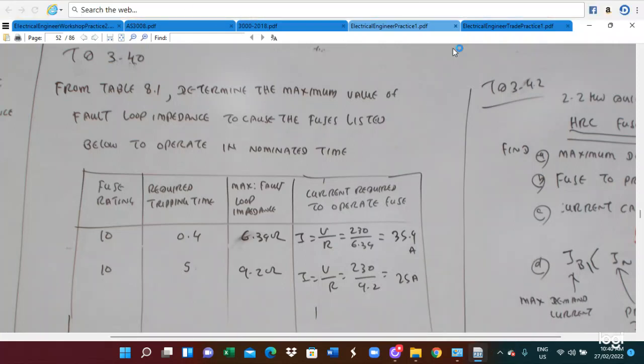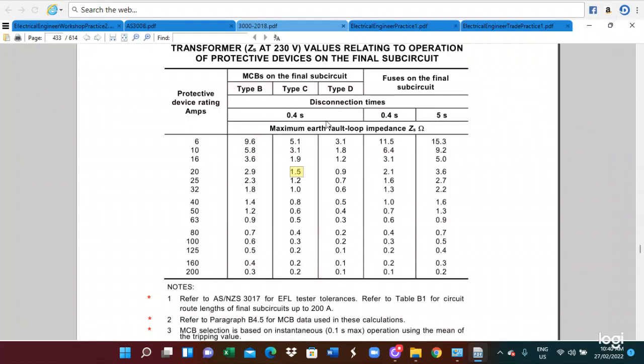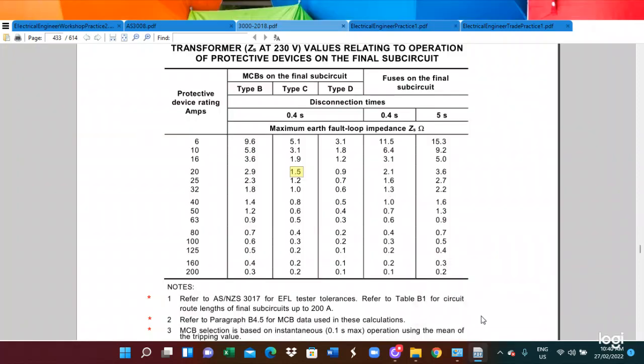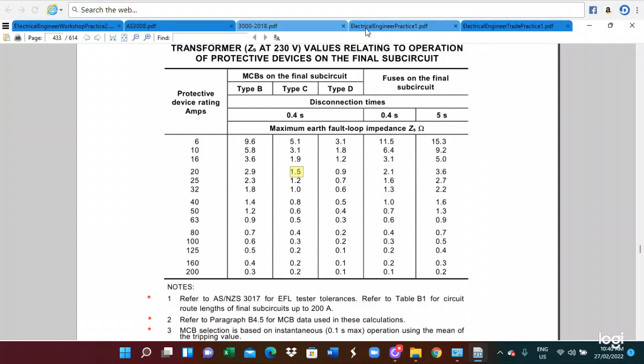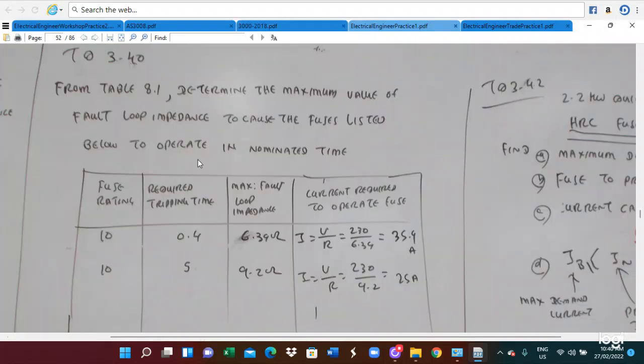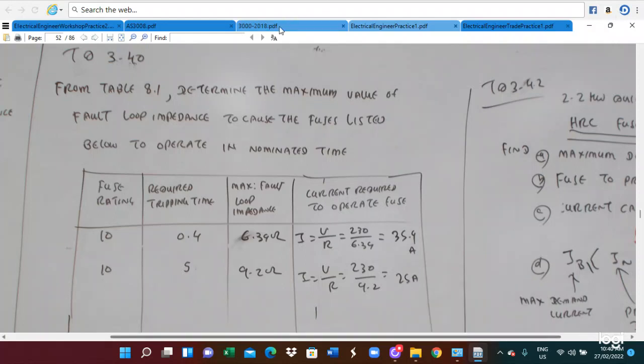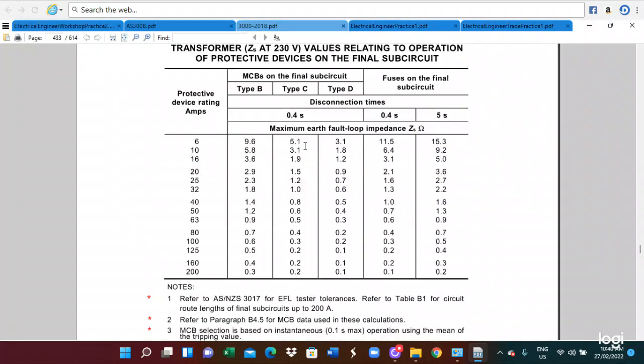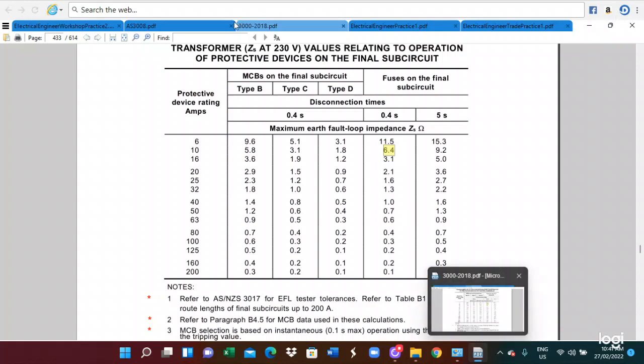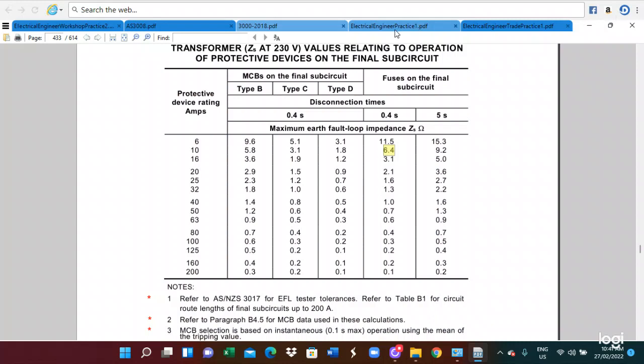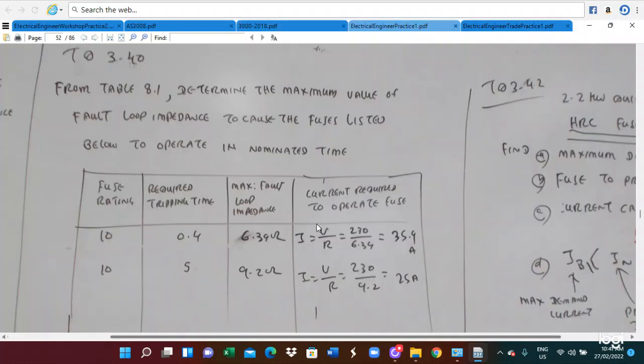Looking at Table 8.1 of AS3000, for a 10A circuit with a tripping time of 0.4 seconds, the maximum loop impedance is 6.4Ω. So 230V divided by 6.4Ω gives the operating current. Then for 10A with a tripping time of 0.4 seconds, we get approximately 35.9A.